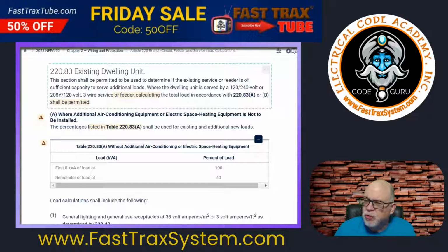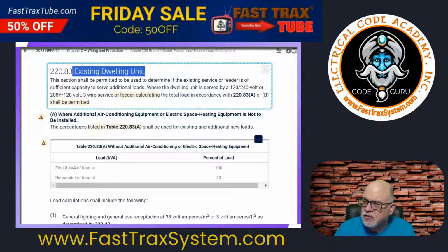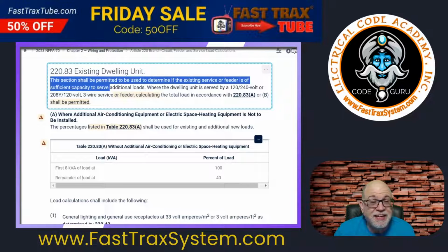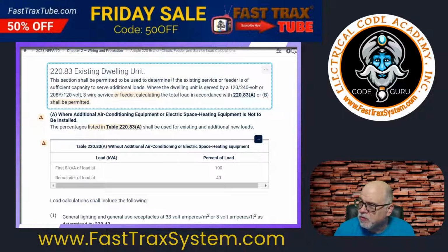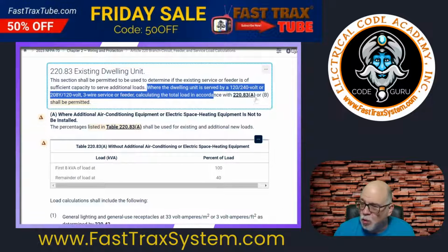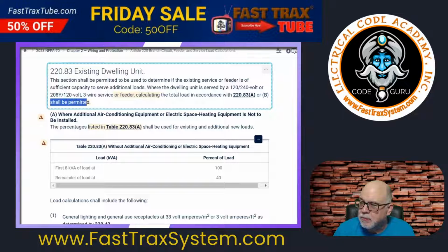So here is 220.83, existing dwelling units. It says this section shall be permitted, so it's a permissive statement, permitted to be used to determine if an existing service or feeder is of sufficient capacity to serve additional loads. It says where the dwelling unit is served by a 120/240 volt or a 208Y/120 volt 3-wire service or feeder, calculating the total load in accordance with 220.83(A) or (B) shall be permitted.